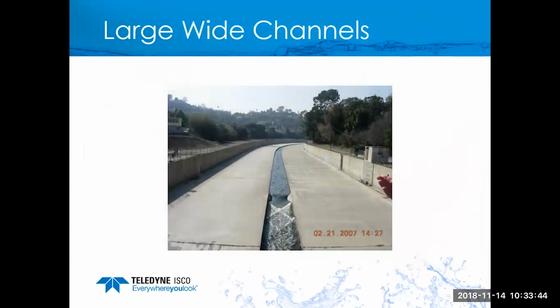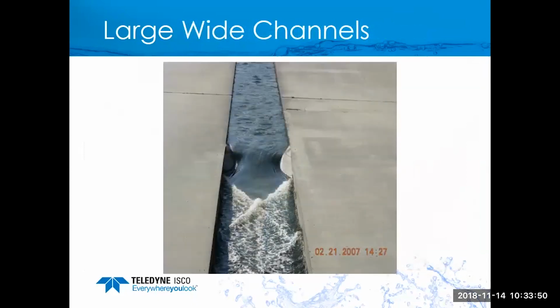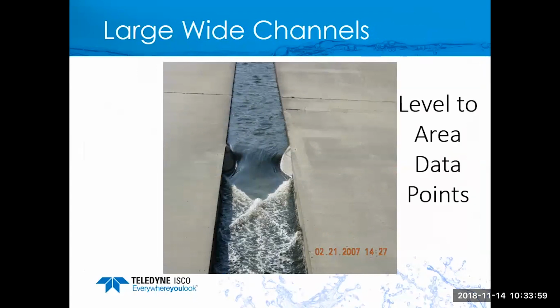Large wide channels. This is in California, so normally they have no flow, but when they get a lot of flow, that whole channel will fill up. They will measure using a laser into this. They would not want to be in this location. They would want to be upstream from that probably. But they can do level to area data points. So you can do level to flow, but you can also do level to area. My level is 2 feet, my area is X. And then you use the velocity of the laser to calculate the flow.